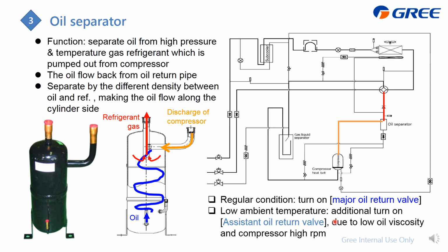And the other one is the assistant oil return valve. The purpose of this one is for low temperature heating, when the oil viscosity is very low because of the low temperature, right? On the other hand, at low temperature heating, we always require the compressor to be at high frequency, and high frequency means it requires more oil for lubrication. If only with this major oil return, that is not enough, so we create another bypass, which is this one, to conduct more oil to flow back to the compressor for lubrication in low temperature heating to ensure reliability.